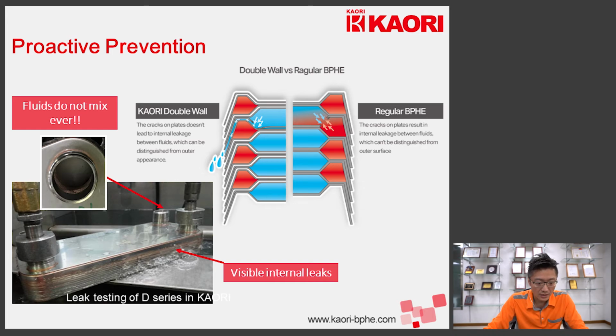If we look at the diagram on the right, there is a simple comparison between a single wall and a double wall scenario. When an internal leakage takes place in a single wall brazed plate heat exchanger, both sides will mix immediately, and we end up with a system failure. So imagine if the fluid is a hot water application which contacts human skin. The system failure can be a disaster.